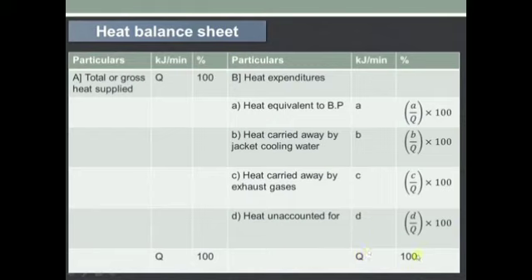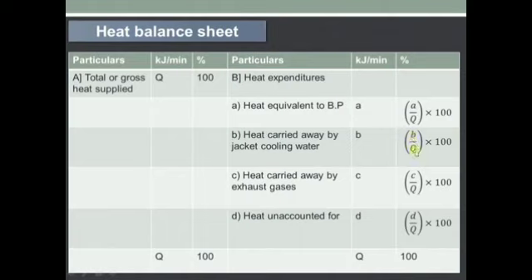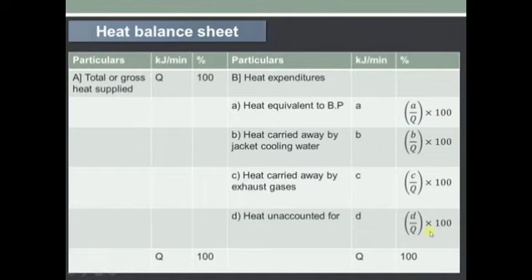For calculating the percentage: heat equivalent to brake power is A divided by total heat supplied Q, multiplied by 100. Heat carried away by jacket cooling water is B divided by Q into 100. Heat carried away by exhaust gases is C divided by Q into 100. And heat unaccounted for is D divided by Q into 100.